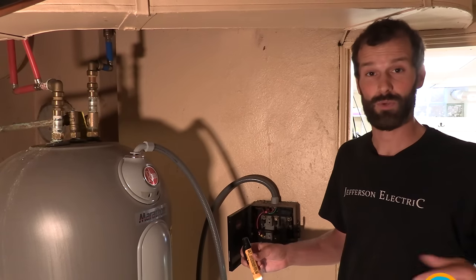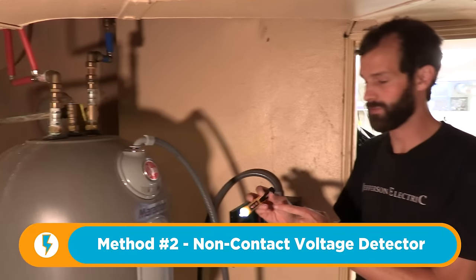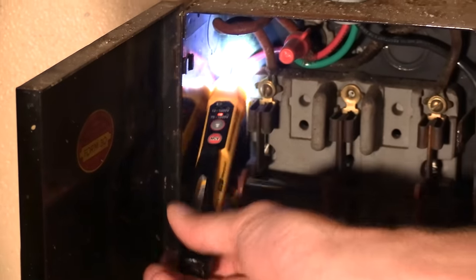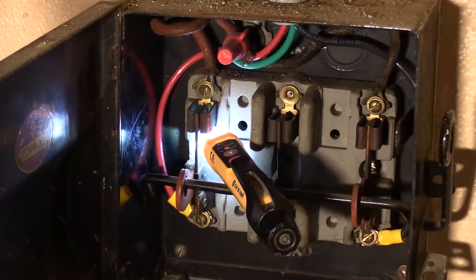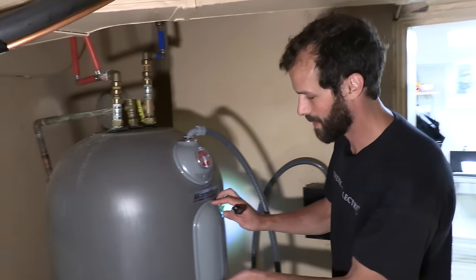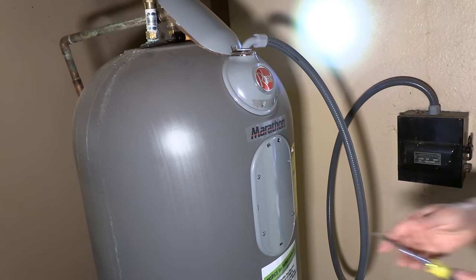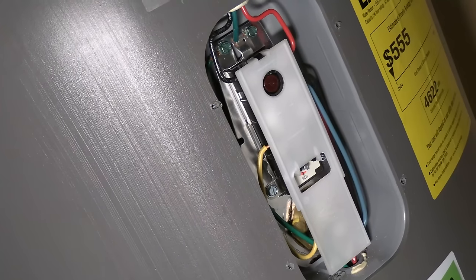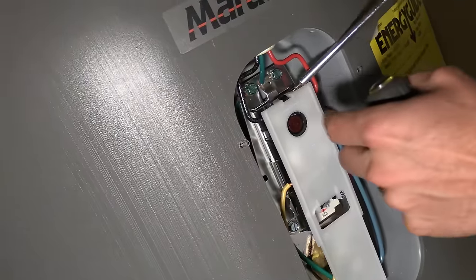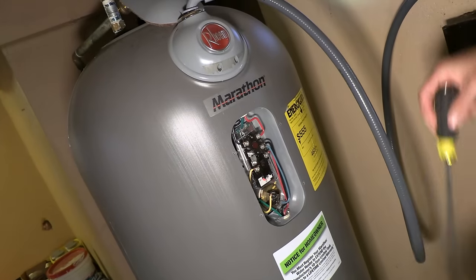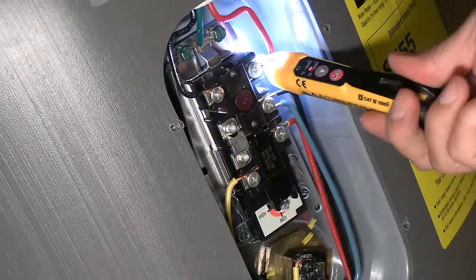A couple different methods and tools you could use to also identify your power is a non-contact voltage detector. Now this is not going to be your most reliable method. But it will chime like that in proximity of power. Get it to sit in there and go flip the breaker. Let's say you don't have an electrical disconnect near your water heater. You can pop either top or bottom element covers off. You can take a flat head screwdriver and remove the four screws. Now that I have the cover off, I want to be careful because the terminals underneath this plastic shield are alive. So using an insulated screwdriver, I'm going to just pop it free. There it is. And I can use any one of the same methods to confirm that power is live.